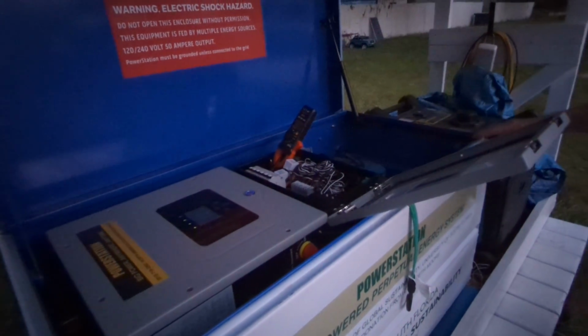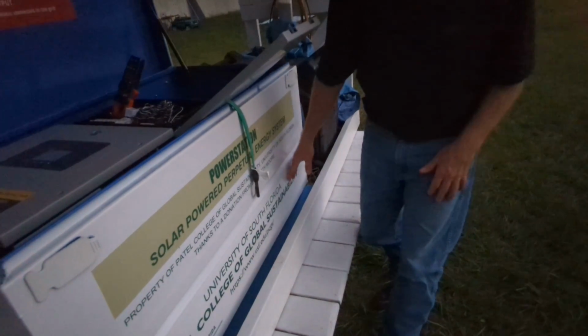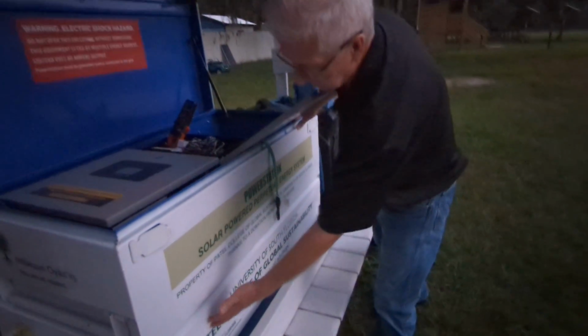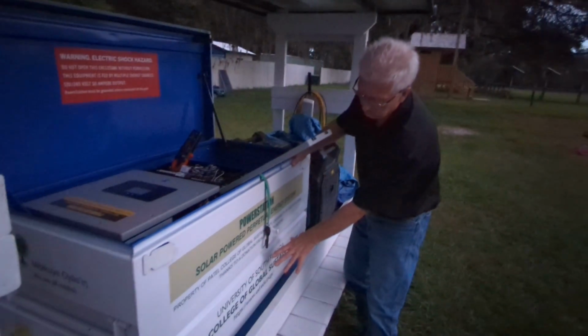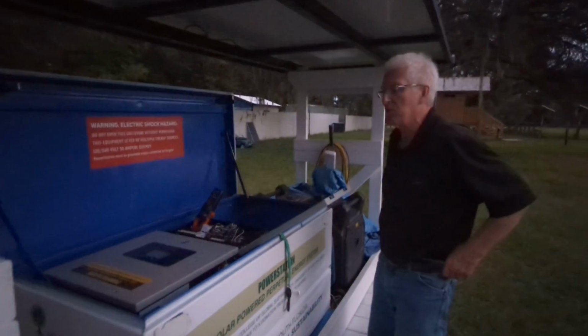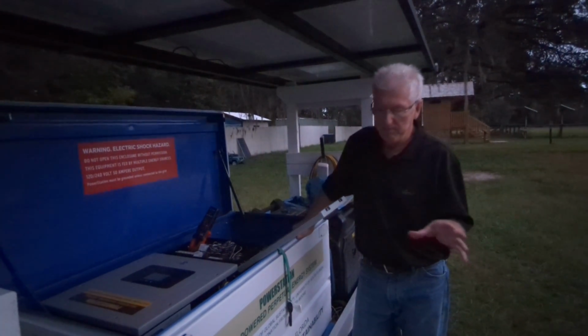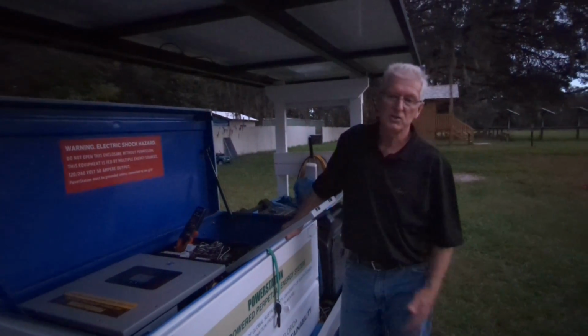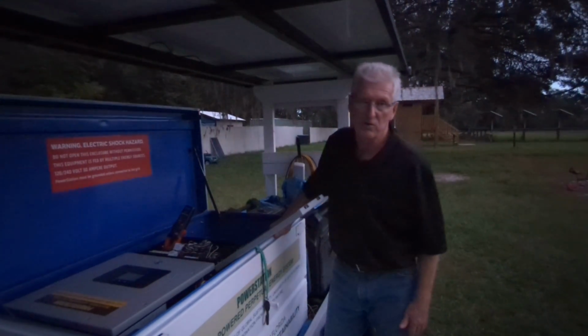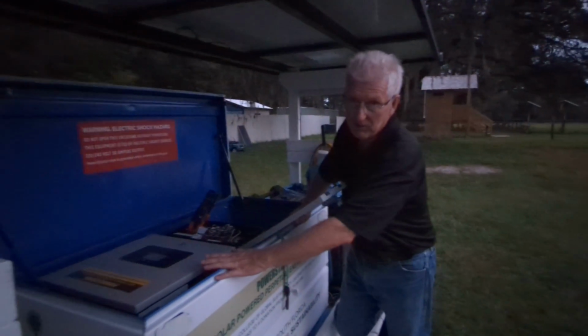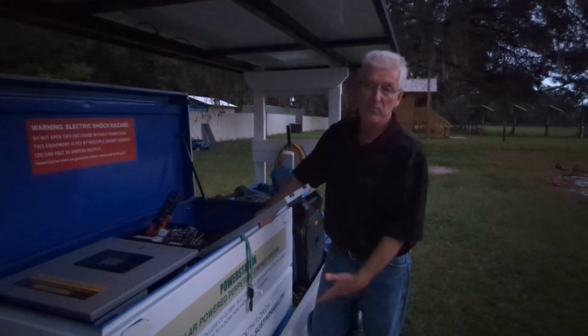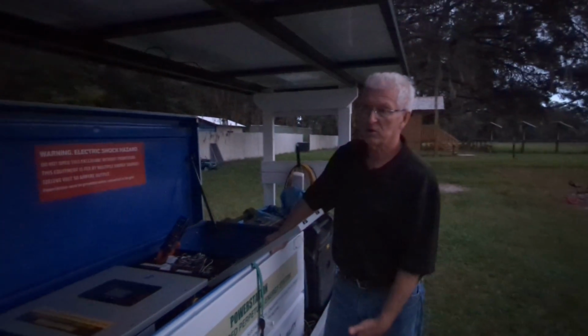And I think we have space underneath here, but the reality is we have two 5 kilowatt batteries in here. The enclosure was designed for up to 4. So we have 10 kilowatt hours here. The rule of thumb is a minimum battery energy storage you'd want to have is 2 times the kilowatt output of your inverter. So we have 10 kilowatt hours from a 5 kilowatt inverter. You would have more energy storage capacity if you had another battery. That would be 15 kilowatt hours.